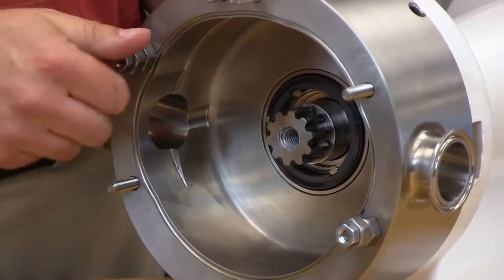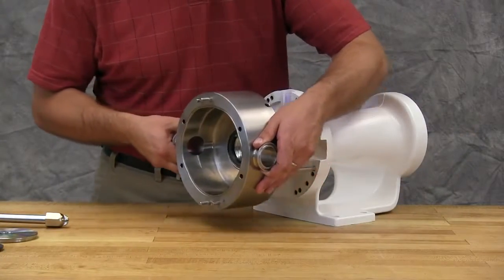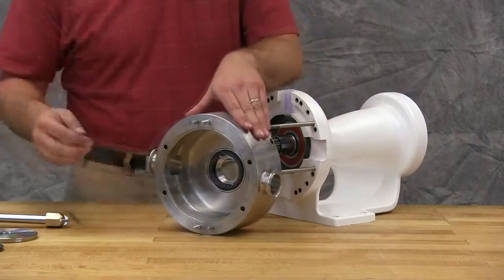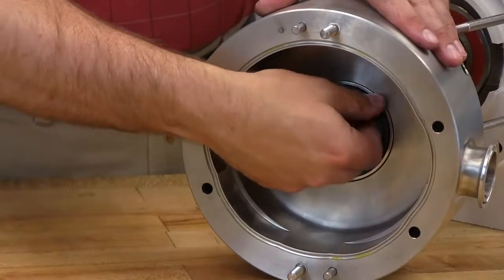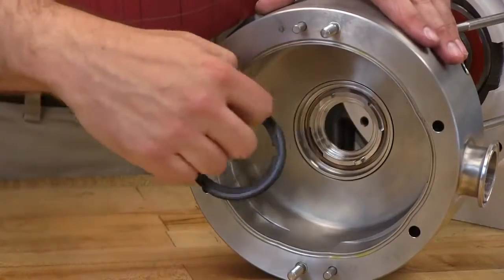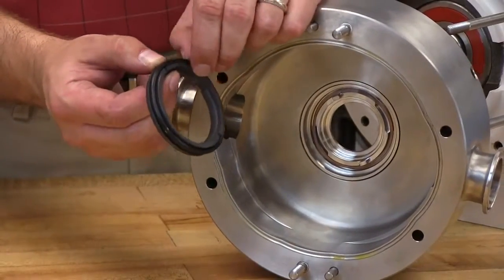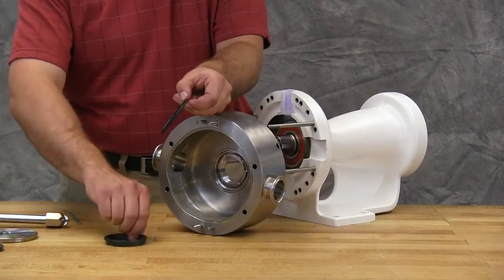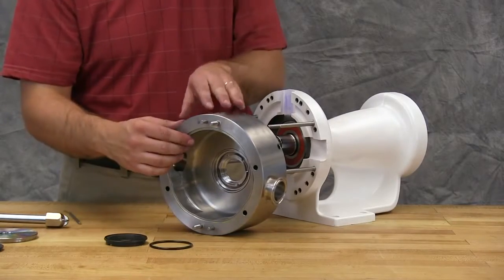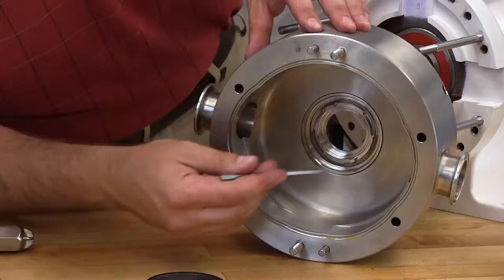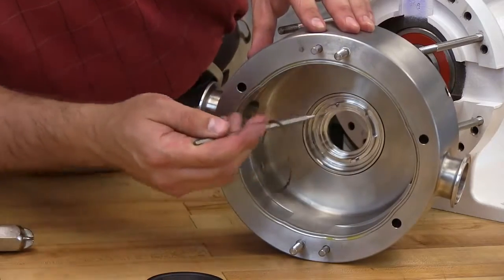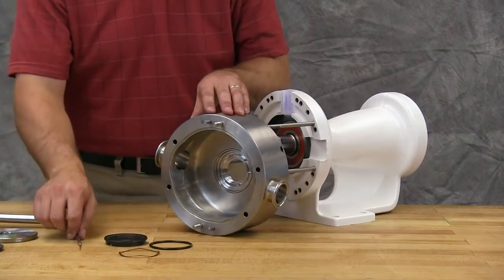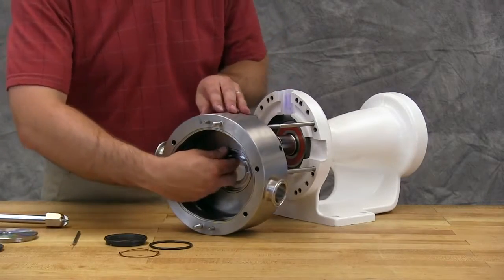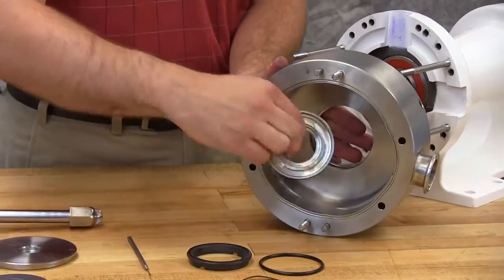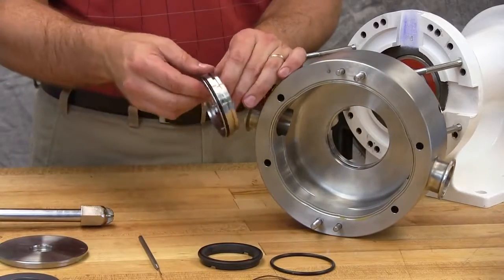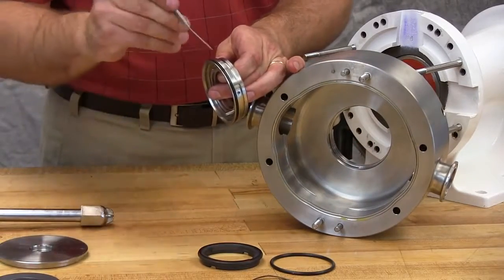Remove the two nuts securing the casing. Remove the casing. For mechanically sealed pumps, carefully remove the stationary face and stationary face O-ring from the seal housing to avoid damaging the face during disassembly and cleaning. Remove the wave spring. The seal housing and seal housing O-ring do not need to be removed from the casing unless the O-ring material of the pump is not compatible with the cleaning solution.